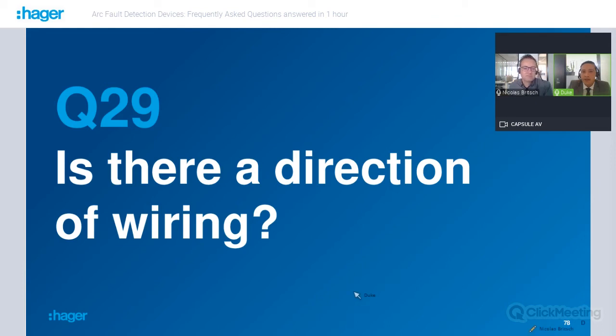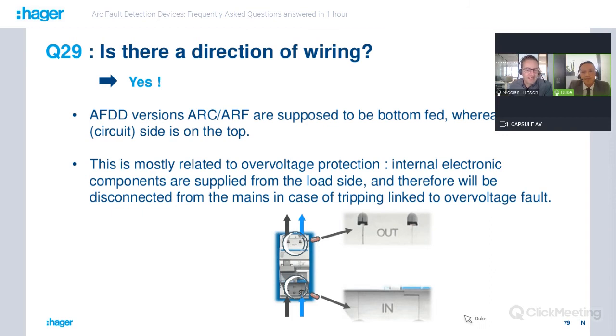And is there a direction of the wiring for AFDD products? Yes, there is a direction of wiring. AFDD versions, ARC or ARF references, are supposed to be bottom fed, whereas the load circuit side is on the top. As you can see, out means circuit side and in is the supply of the product, the incoming supply. This is mostly related to the overvoltage protection because the internal electronic components of the AFDD are supplied from the load side. It means that they will be disconnected from the mains in case of tripping linked to an overvoltage fault. That's why we have to respect this direction of wiring, to be sure that the electronics are disconnected from the power supply in case of overvoltage fault.